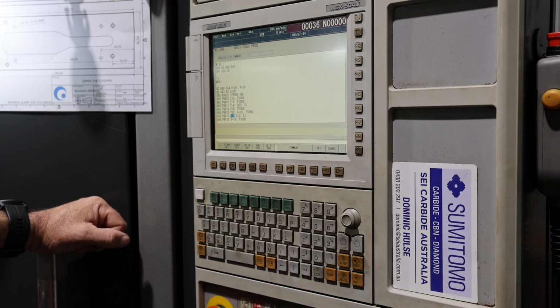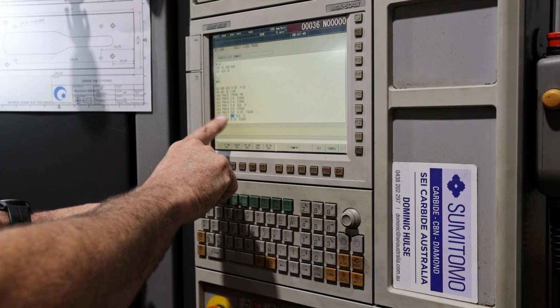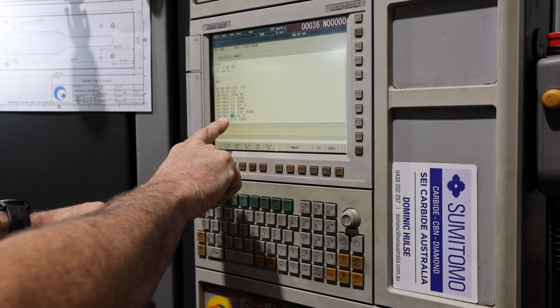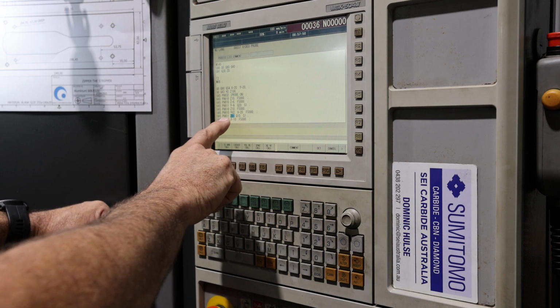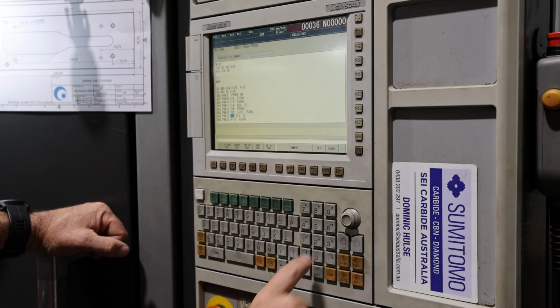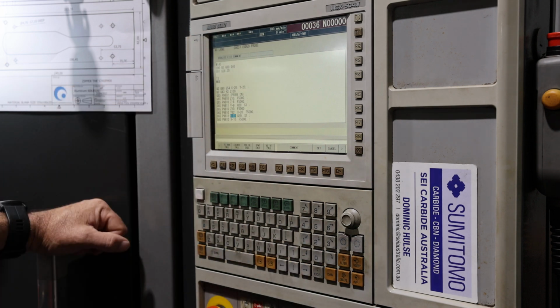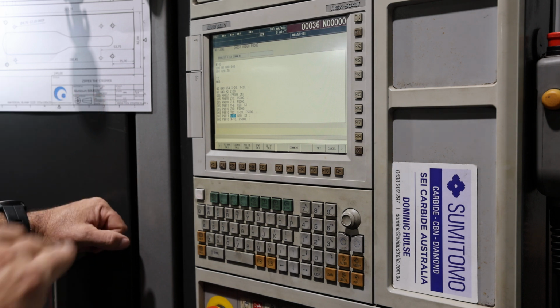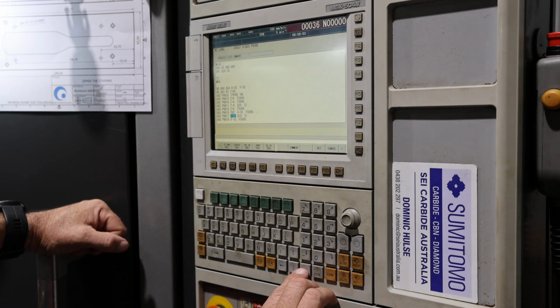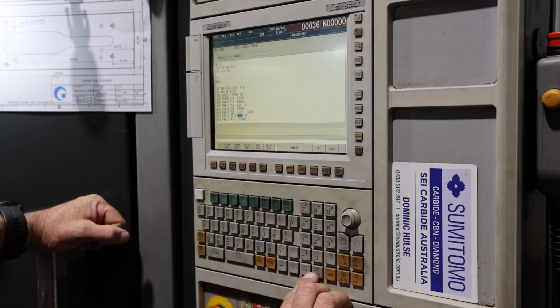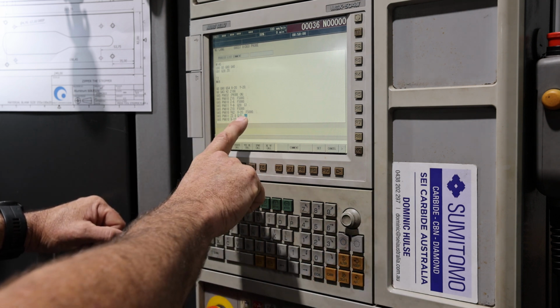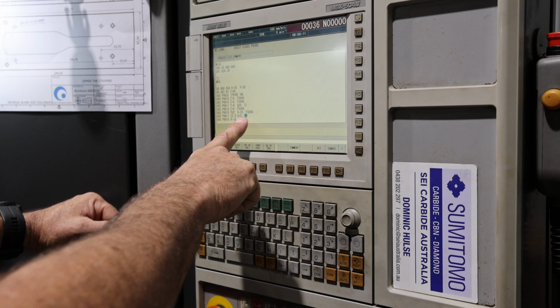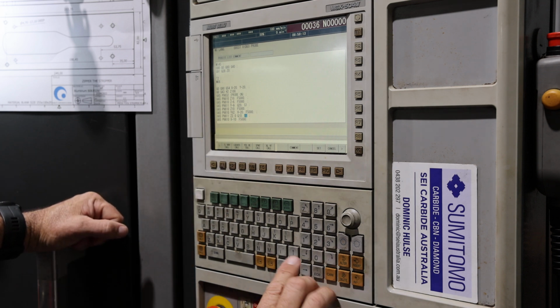We have 2mm to take off the job, so when we come down and teach our Z on our P9811, which is our single axis reference base, we can put a value in there of Z positive 2. So when the probe comes down and touches the job, it'll teach the G54 that the probe is actually at 2mm. We have a tolerance again of 10, which is sufficient for your Z-axis, and an offset. We're using the offset S1, which is G54.